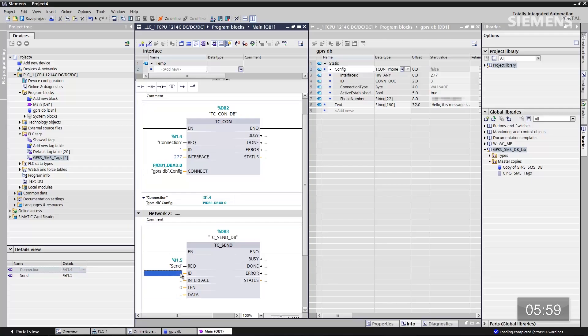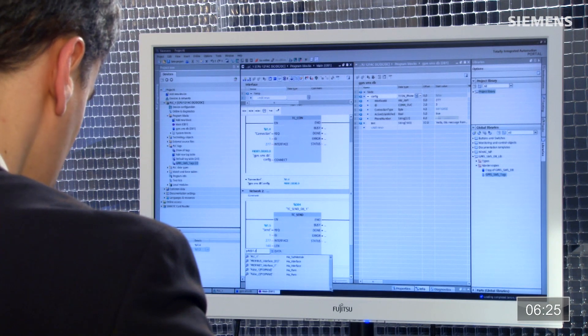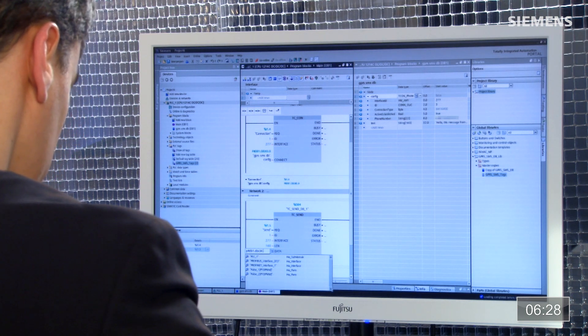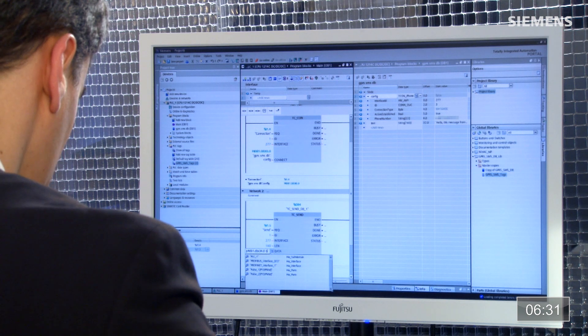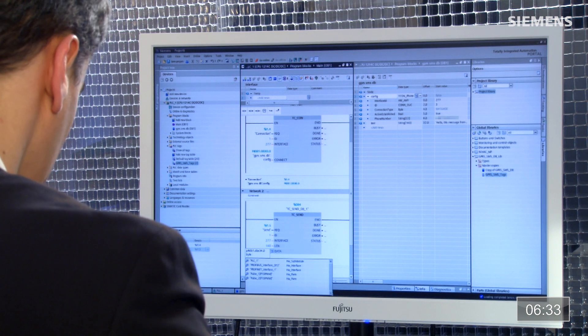Go to ID — click 1, the hardware identifier 277, and the length is 160. Then I'm going to do something a little bit different: I'm going to create an actual pointer so that we can have just the text message with no header or footer that's not supposed to be there. I can do that just by typing this out: P#DB1.DBX32.0 BYTE 160. So now our send block is complete.